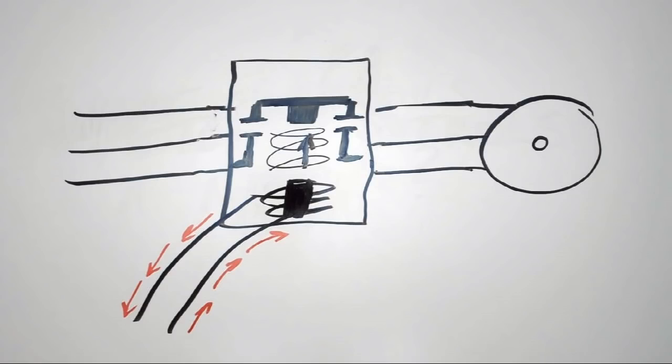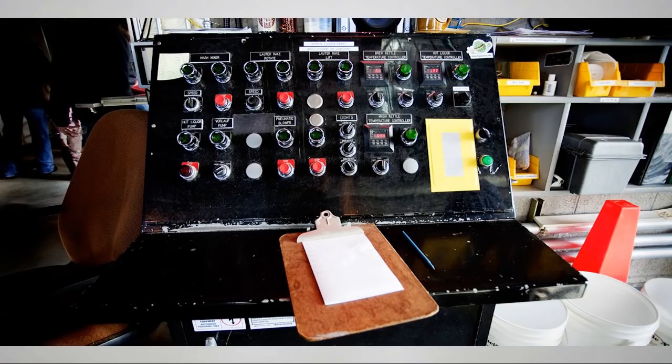So what's the point of all this? Well, it allows for remote operation of the contactor, which thus allows remote operation of the motor. If you put something like a push button on the other side of the circuit that is connected to the contactor's coil, then you can turn on the coil from wherever you want. Imagine a control station with 40 push buttons installed on it, and now the operator can stand there and control all the motors around the facility without even taking a step.